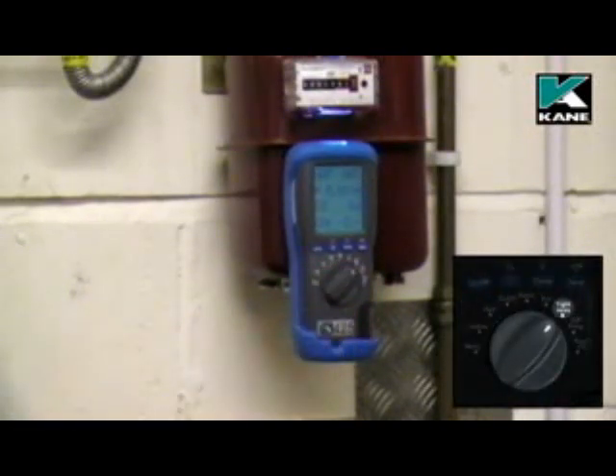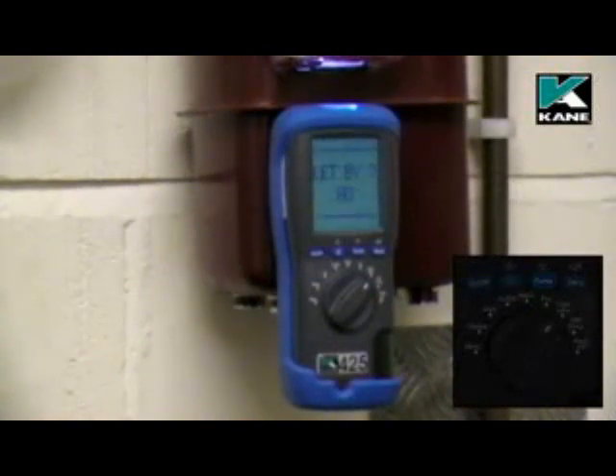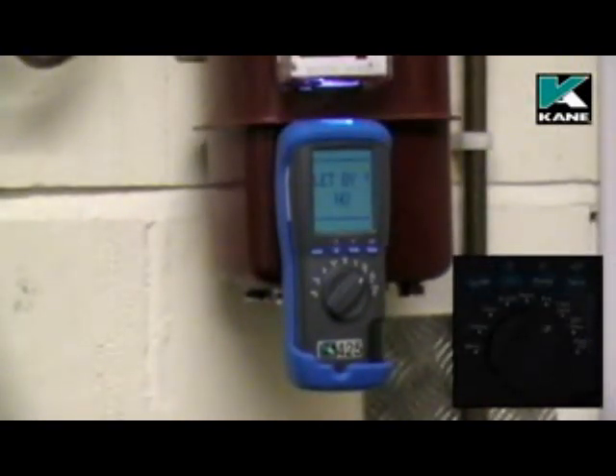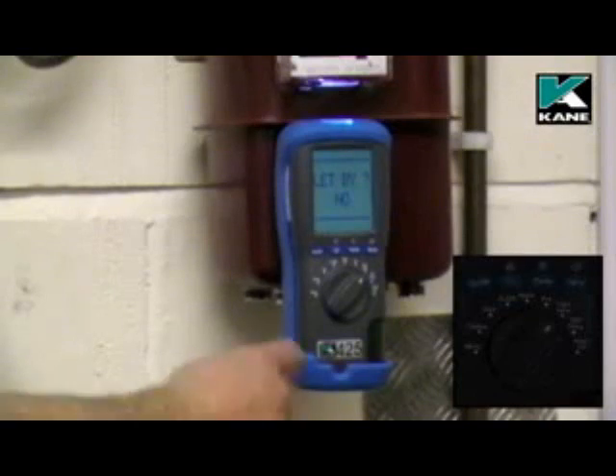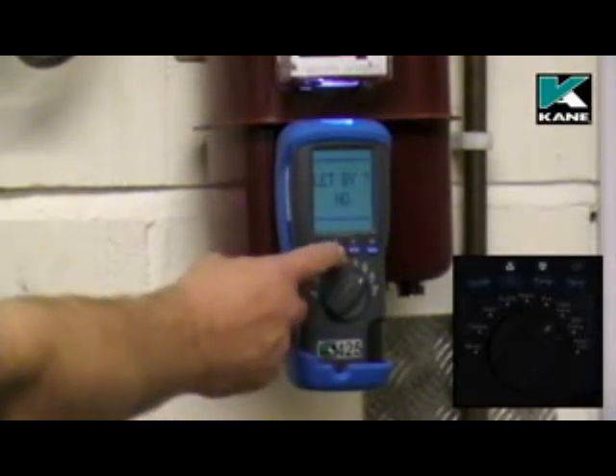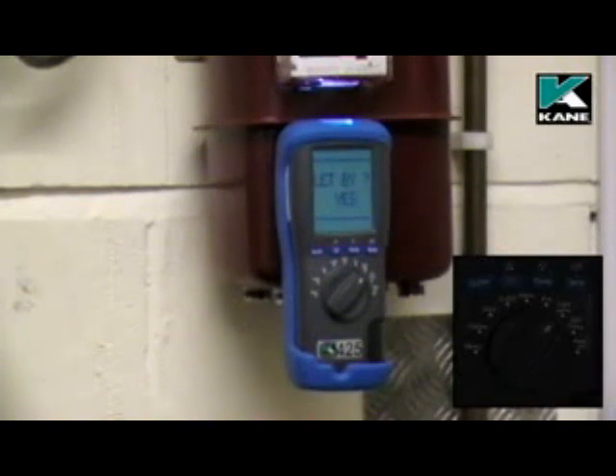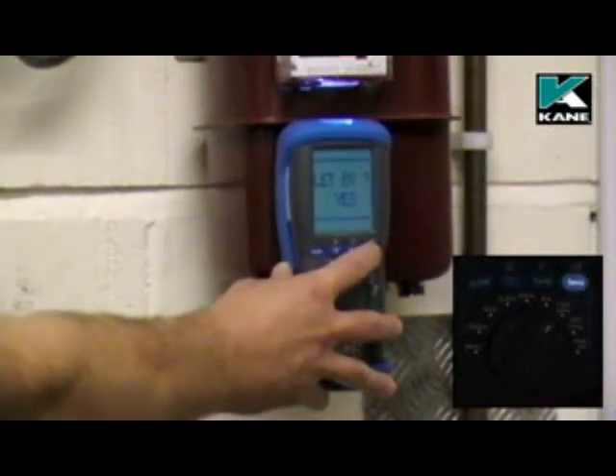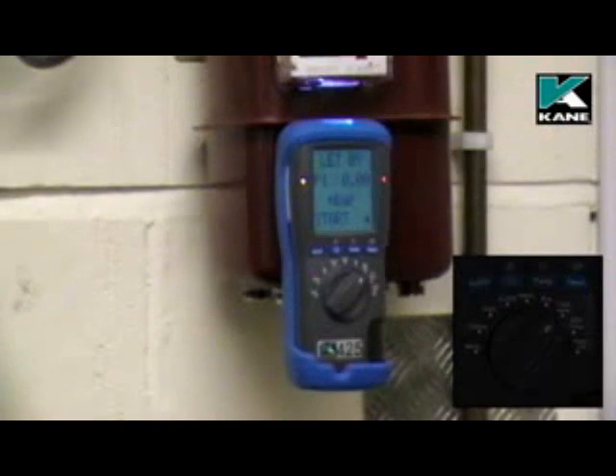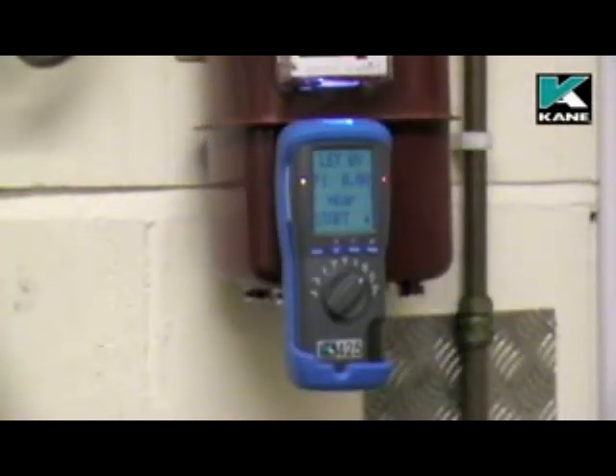Tightness test. Select tightness on the rotary switch. The pump stops and it tells you to press the pump button to zero the pressure sensor. When you do this, make sure you have no hose connected to the analyzer. It asks us if we want to do a let-by test. Use either of the scroll buttons to change that to yes, and then press the send button or enter. So it's now ready for us to connect the hose.